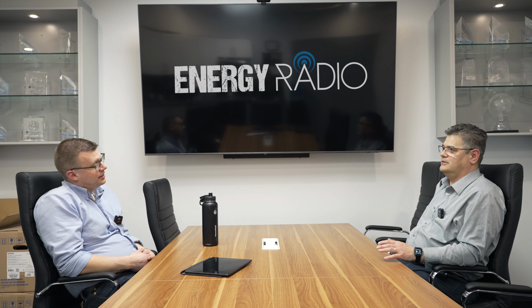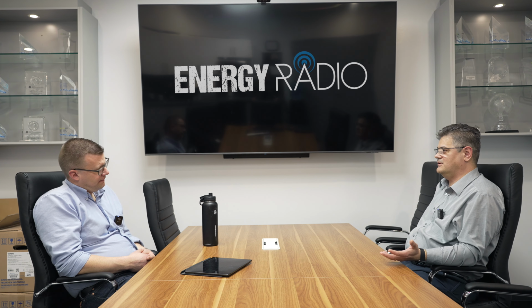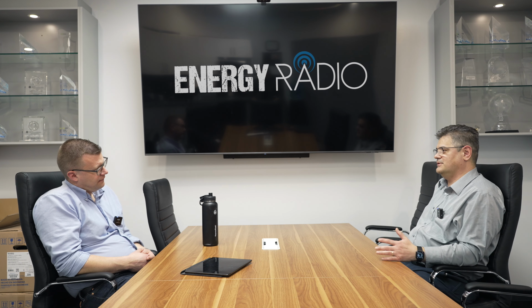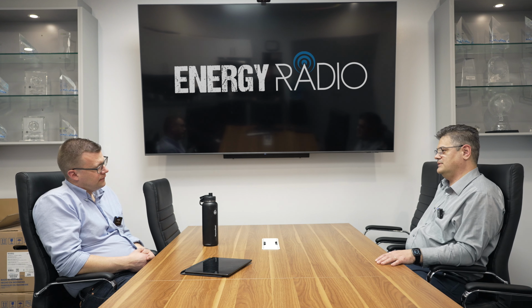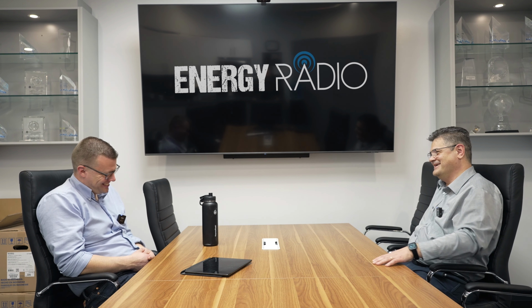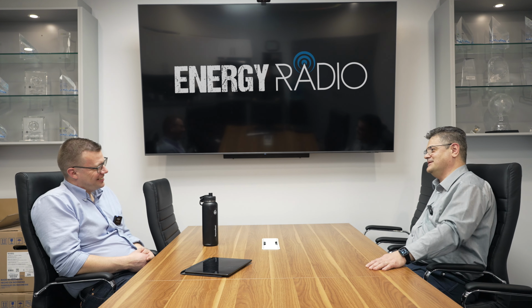Another thing we did since then—if you remember when we designed the cogen, we left provisions in the field for a blackout generator connection box. We bought and installed that generator because during an extended power outage, we were saying we're going to rent a generator, but when everybody wants a generator, how do you get that generator on site quick enough?